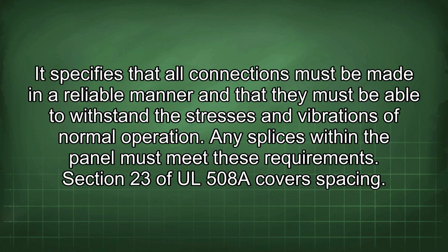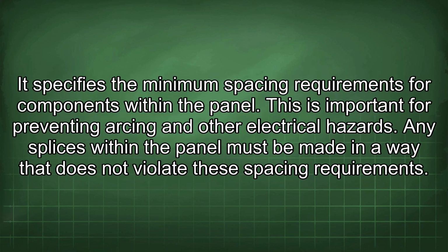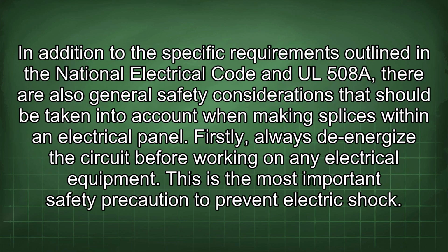Section 23 of UL 508A covers spacing. It specifies the minimum spacing requirements for components within the panel. This is important for preventing arcing and other electrical hazards. Any splices within the panel must be made in a way that does not violate these spacing requirements. In addition to the specific requirements outlined in the National Electrical Code and UL 508A, there are also general safety considerations that should be taken into account when making splices within an electrical panel.